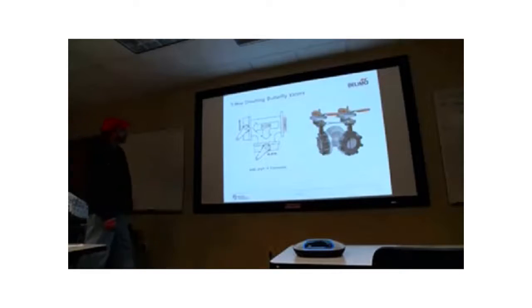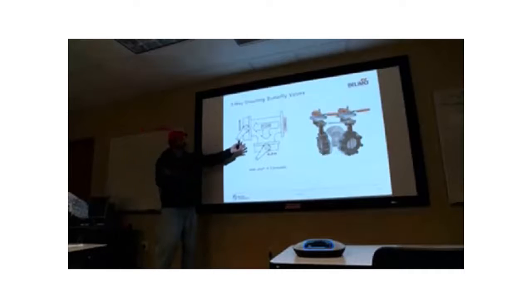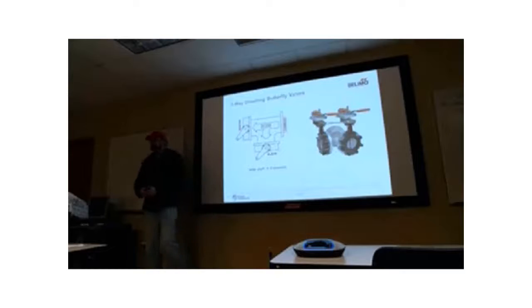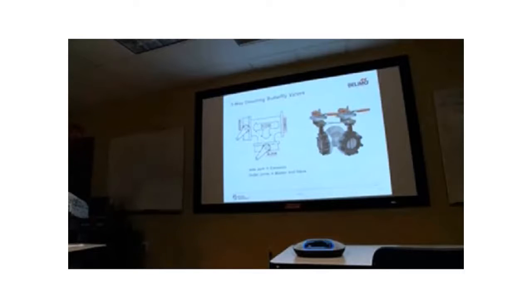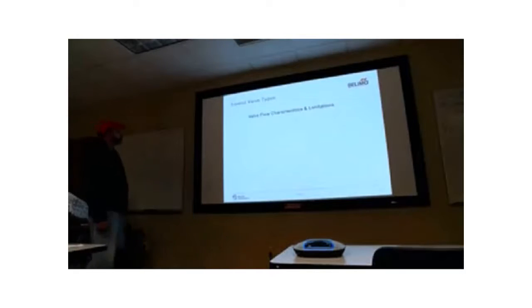So, the diverting butterfly valve, same setup really, right? Only the flow is going the other way, right? The flow is now coming into the valve. It's either going through the master or it's being diverted to the slave. Okay.